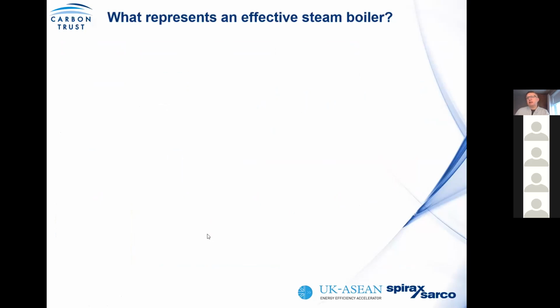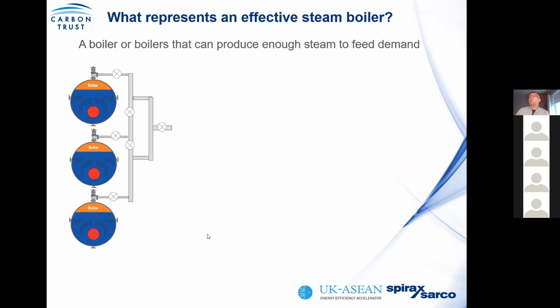So let's start with generation. So you have a boiler, or in reality, you probably have multiple boilers which are supporting your site steam system. You may have a scenario where we have one duty boiler or standby boilers. And the function of the standby boiler is to ensure that your steam distribution pressure is being maintained at a constant. What we have found from our experience is that the very nature in which you use steam could cause your standby boiler to intermittently start-stop to basically counteract a pressure reduction.